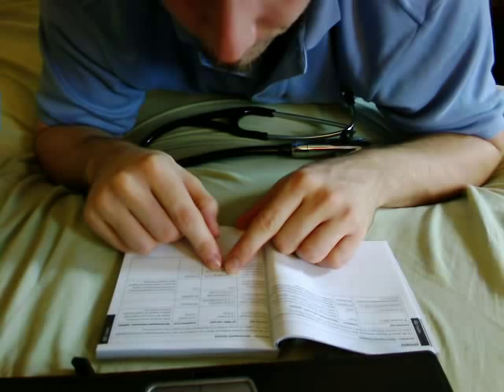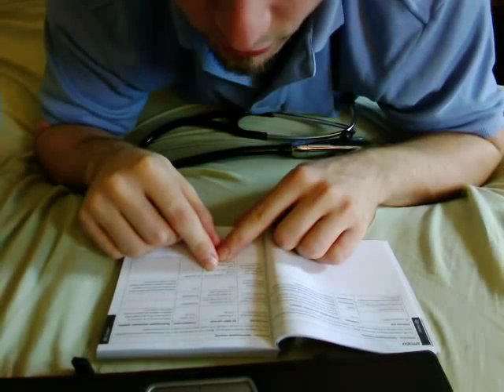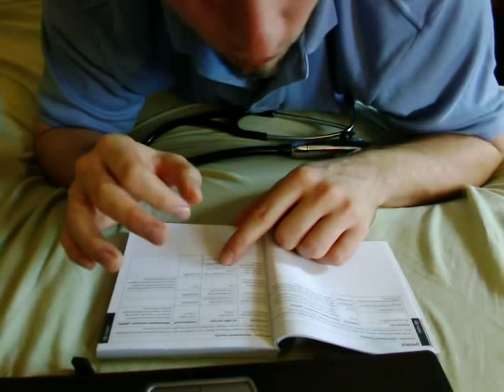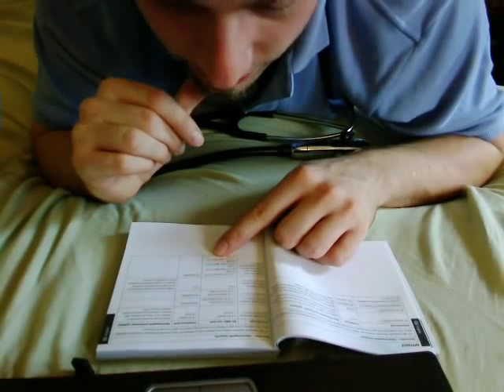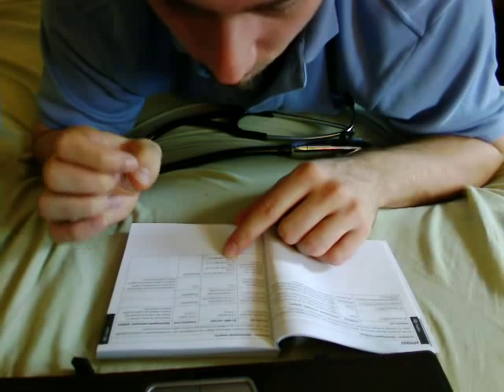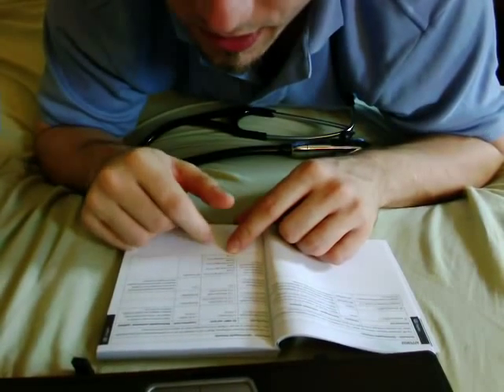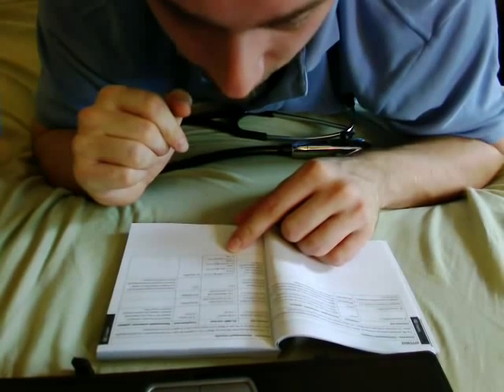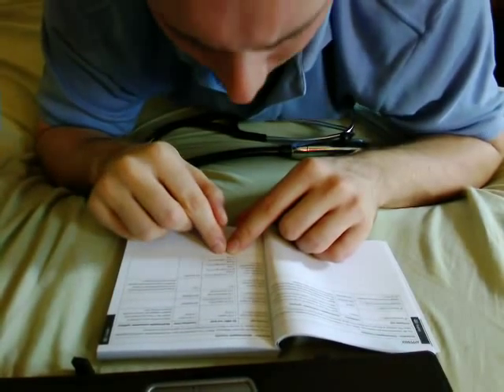The IEC 60601 test levels for IEC 61000-4-11 were: less than 5% UT, which is greater than 95% dip in UT for 0.5 cycle; 40% UT which is a 60% dip in UT for 5 cycles; 70% UT which is a 30% dip in UT for 25 cycles; and finally less than 5% UT again — greater than 95% dip in UT — but for a 5-second duration rather than 0.5 cycle. No compliance levels were applicable and no electromagnetic environment guidelines were indicated.